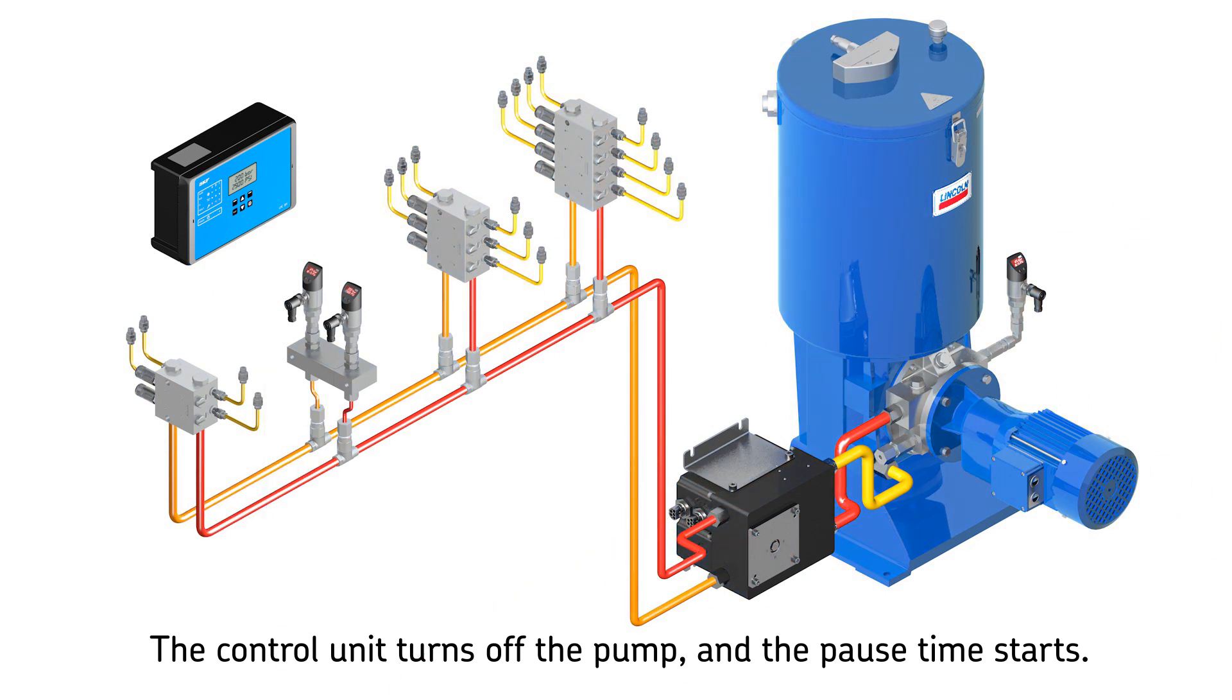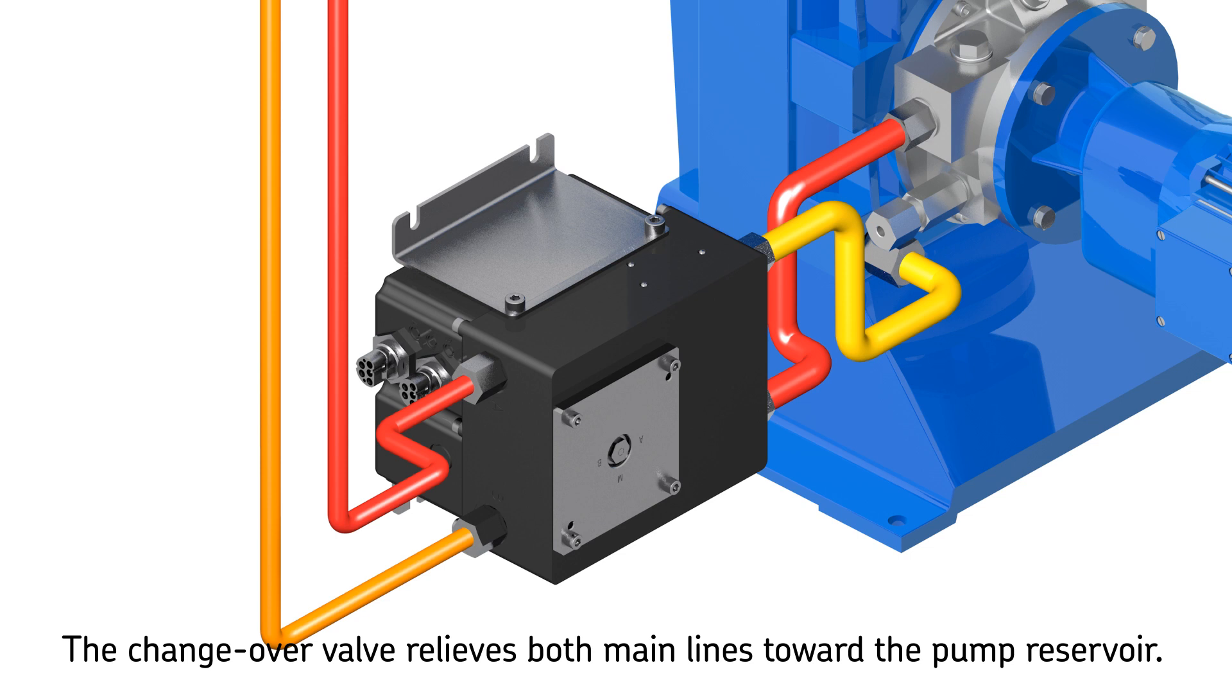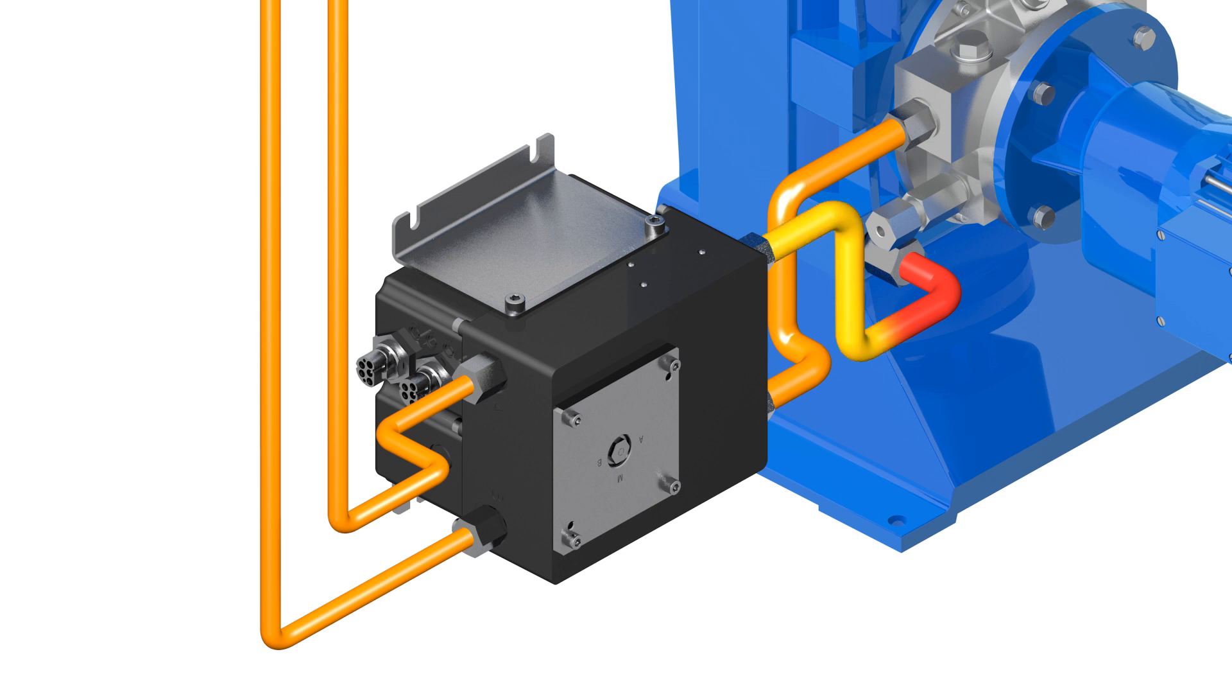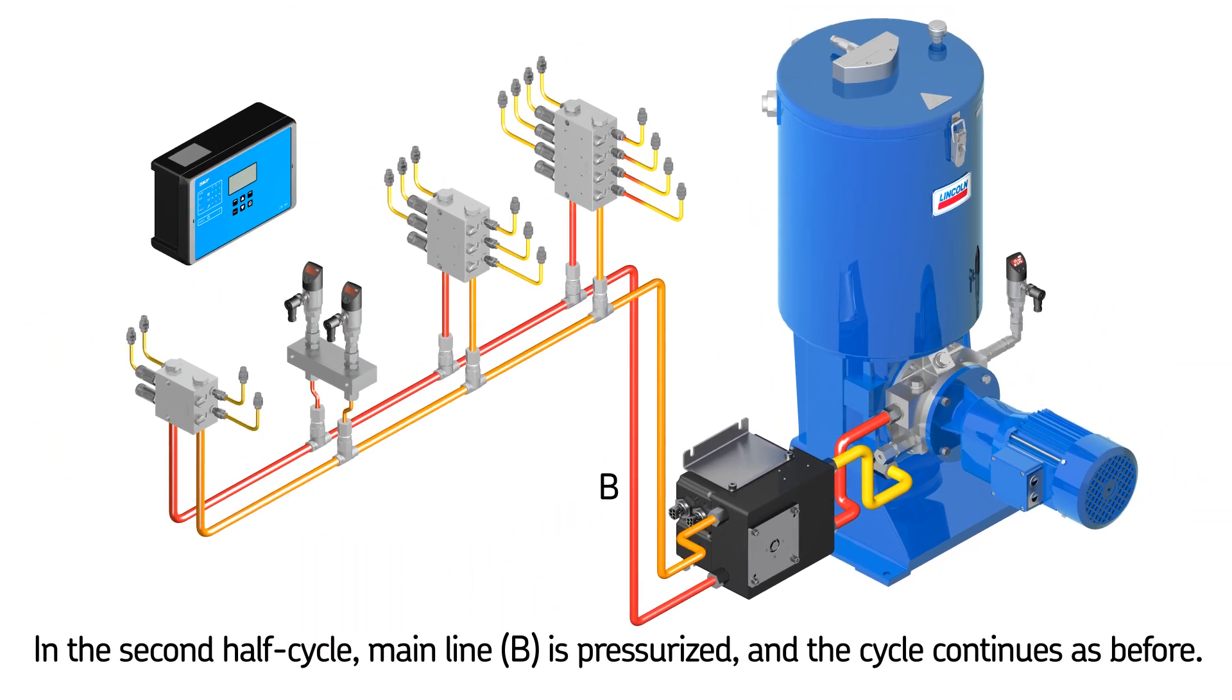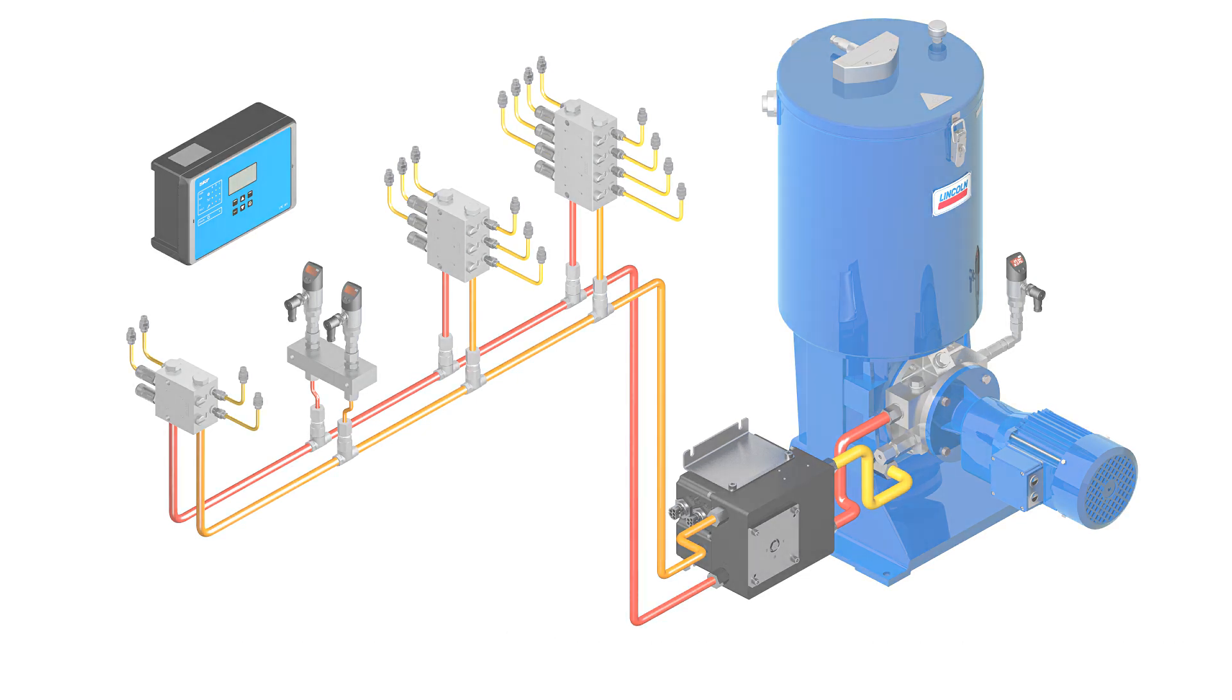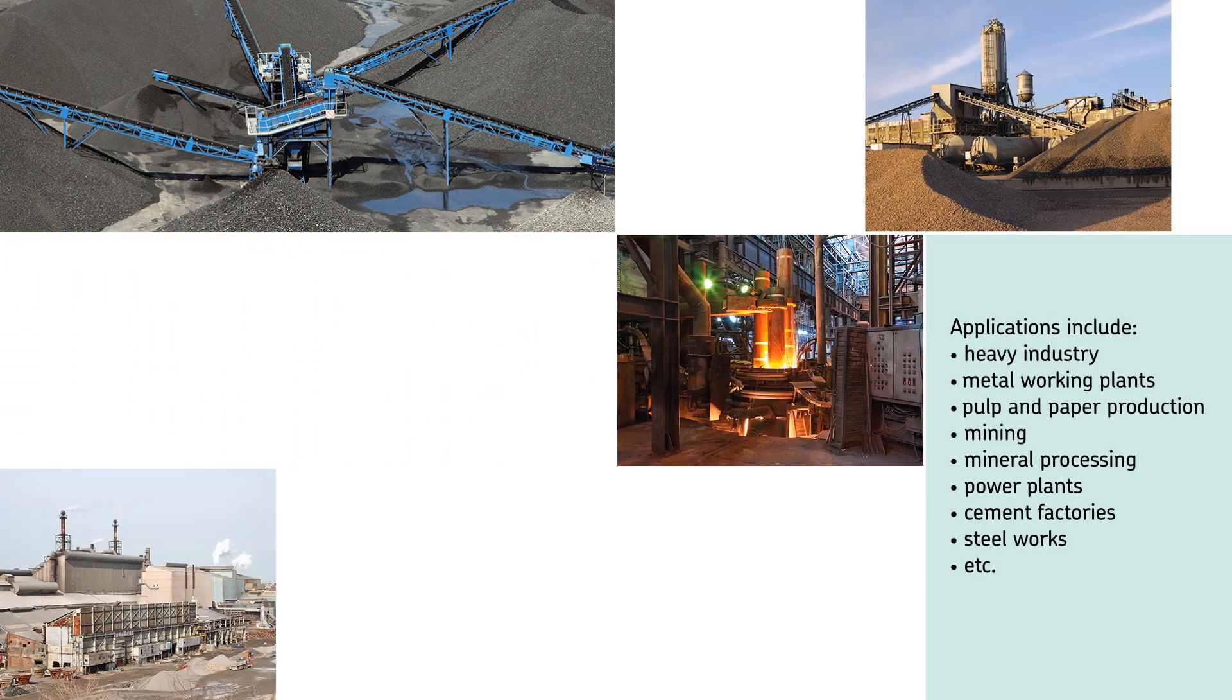At this stage, half of the lubrication points have been lubricated. System pressure relief works by first relieving the pressure line between pump and changeover valve into one main line, then both main lines are relieved simultaneously. In the second half-cycle, main line B is pressurized and the cycle continues as before.